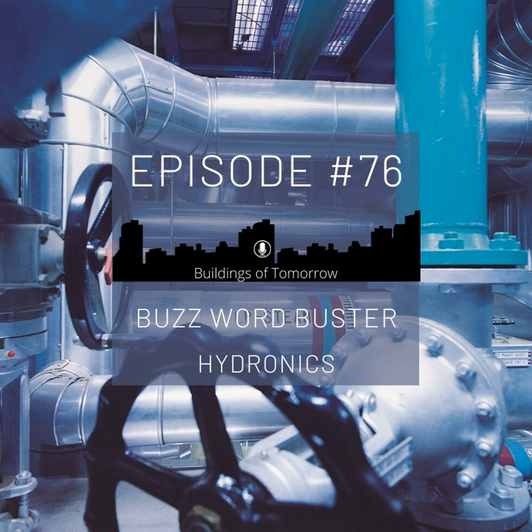Perfect. So let's have a look at a couple of different circuits, because we've talked about valves, and now a little bit about the system, but the circuit itself is really the all-encompassing part of this individual consumer. So not just the valve itself, but the coils and any other temperature or energy delivery device into the airflow, etc. We have two different circuits here on my list, so we'll go one at a time, and you could give us a little bit of an explanation. That would be great. So the first I have is throttling circuit.